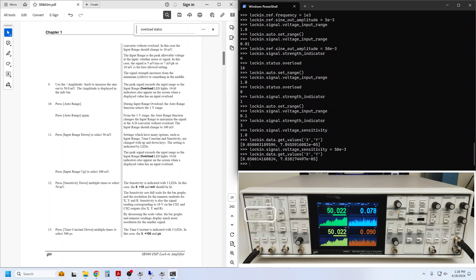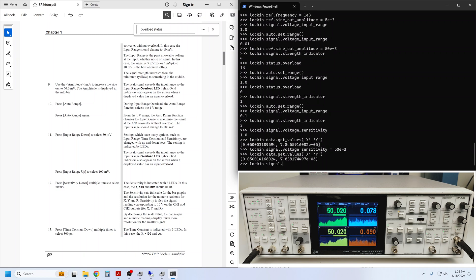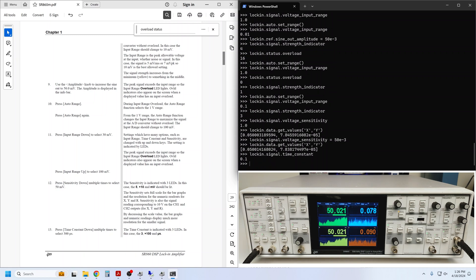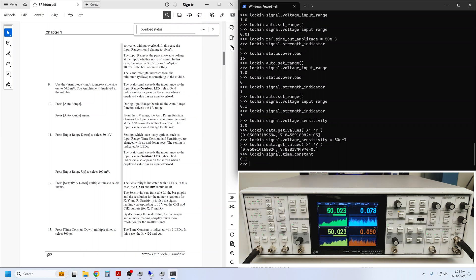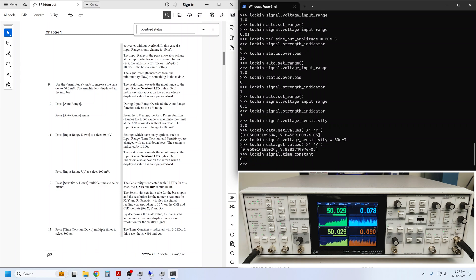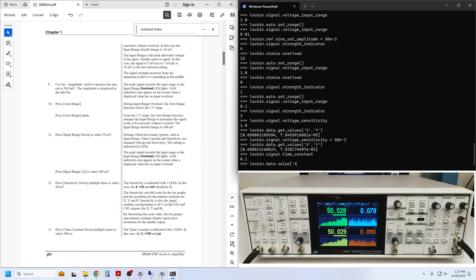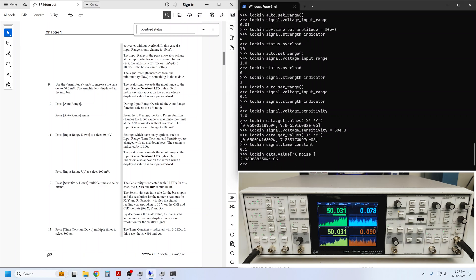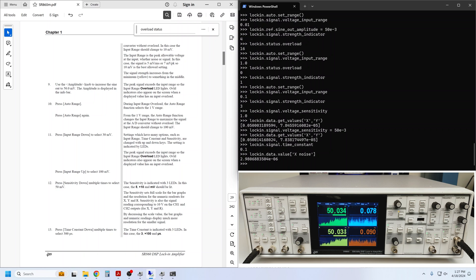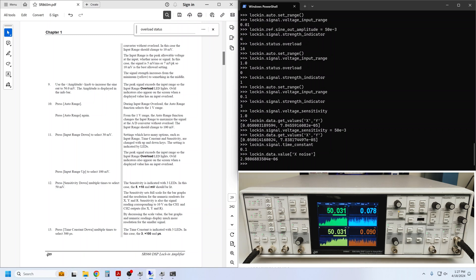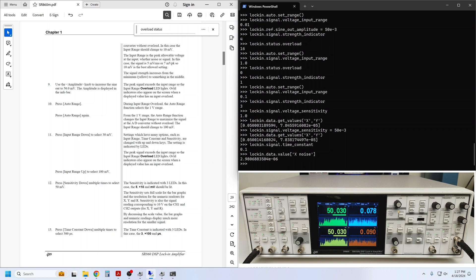Next, we are supposed to adjust the time constant. The default time constant is 100 ms. This also lives in the signal component. We want to see how the choice of time constant affects the measurement noise, which is easily visible on the front panel numeric displays and trend graphs just by watching how much the values bounce around. But can we obtain that information remotely? Of course. Remember the data.value command? We can ask about the X or Y noise. The lock-in continuously calculates X_noise and Y_noise as the RMS deviation of X and Y about their mean values averaged over about 200 time constants. This is 20 seconds for a time constant of 100 milliseconds. Since we've been sitting in this configuration for much longer than that, I trust the value here. I can also see the values on the front panel bouncing around with a few microvolt noise.